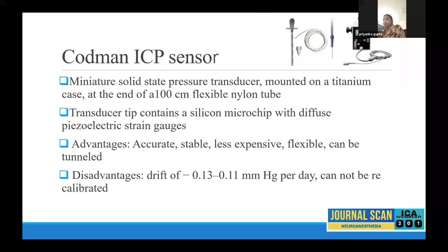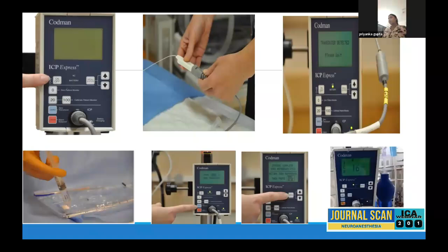So, this is the ICP monitor attached with the cable. First we switch it on. We connect this cable to the ICP sensor here. Then we press the zeroing, and it will say that the transducer is detected. Here the tip of the transducer is submerged in saline horizontally. Now we press the zeroing. Once it is zeroed, the neurosurgeon or whoever is performing does the burr hole and then inserts it. So this is the only time it can be zeroed. After that, it cannot be zeroed.